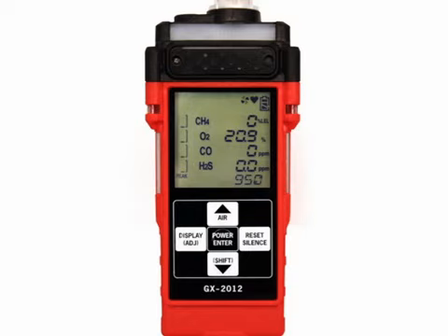It does this by turning off the % LEL sensor power temporarily when it determines that a % LEL overscale, more than 100% LEL, concentration of combustible gas is present that may damage the sensor. When this happens, over is displayed below the gas list, and the display units to the right of the combustible gas channel change to % volume.